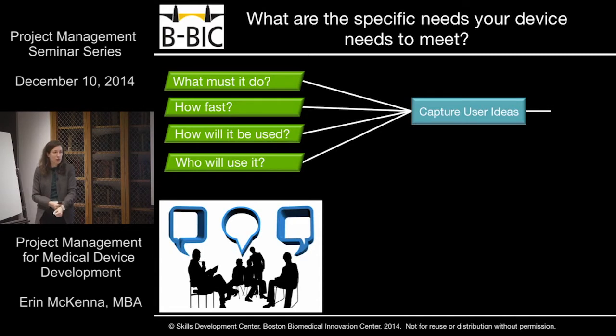One of the most straightforward ways is to think about who your users are and recognize that that's probably going to be more than one person. While it may be primarily one physician or one surgeon that is doing the heavy lifting when it comes to using your device, you still want to count a patient as a user. Or your patient may be a user if you're designing something that's supposed to have a patient interface that they can manage. Glucose monitors would be a good example of that.